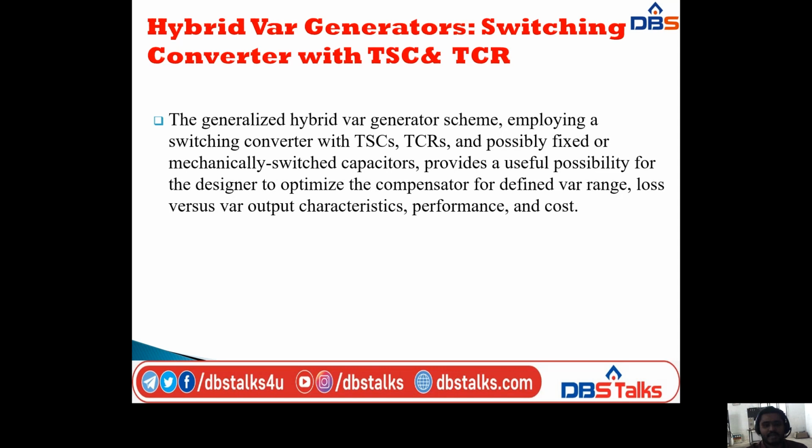So the generalized hybrid VAR generator scheme employing a switching converter with TSCs and TCRs and possibly fixed or mechanically switched capacitors provides a useful possibility for the designer to optimize the compensator for defined VAR range, loss versus VAR output characteristics, performance and cost. So further, we are taking hybrid VAR generators, that is switching converter with TSC and TCR combination. This is the concept for hybrid VAR generators.